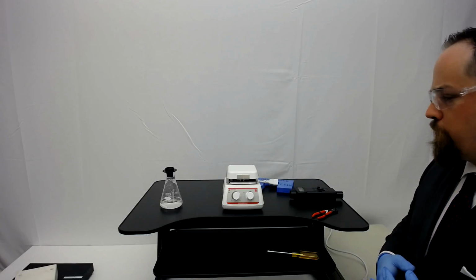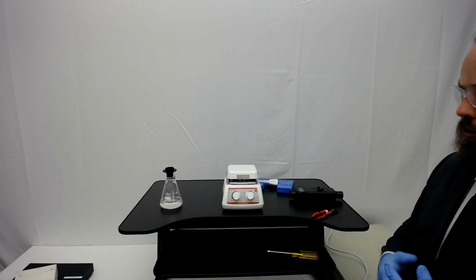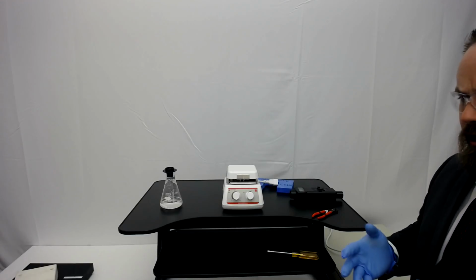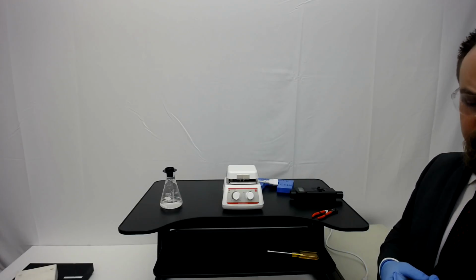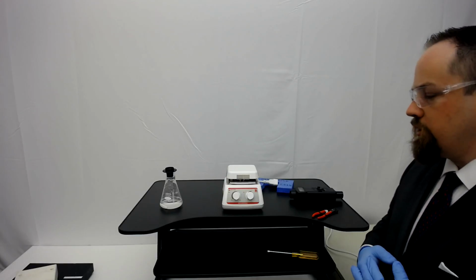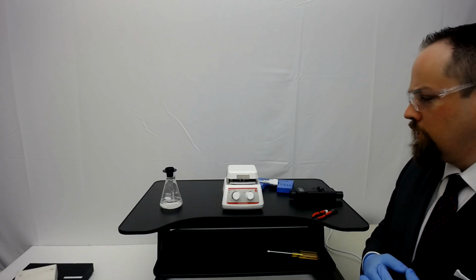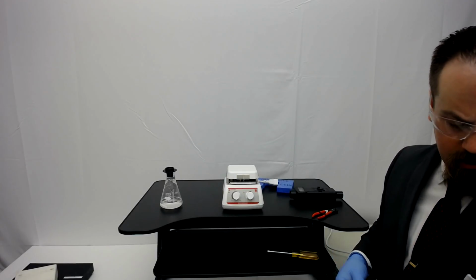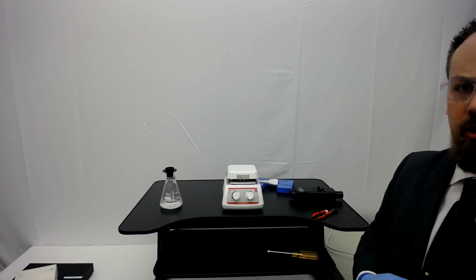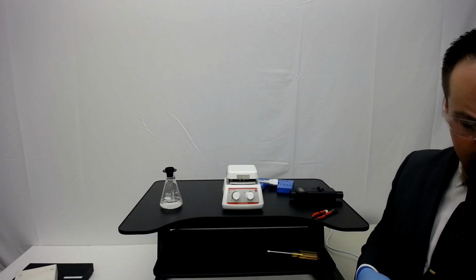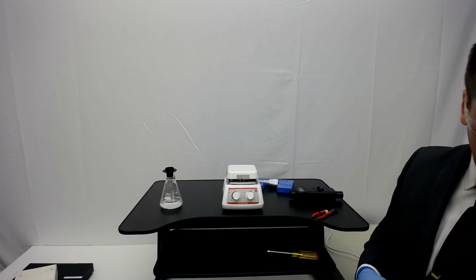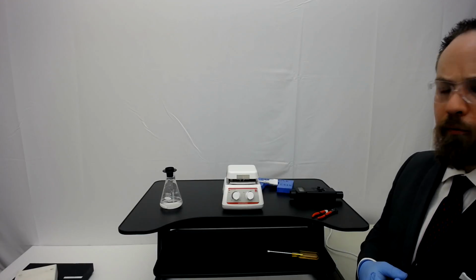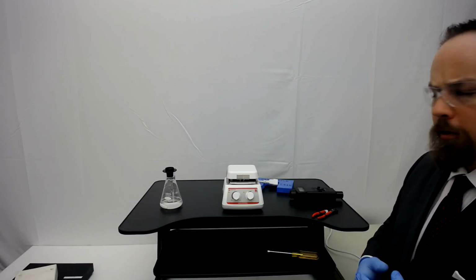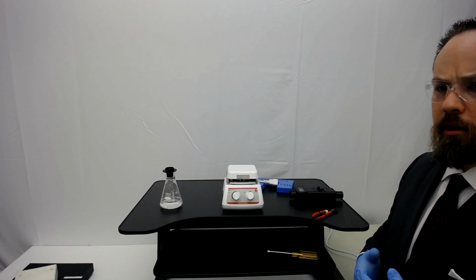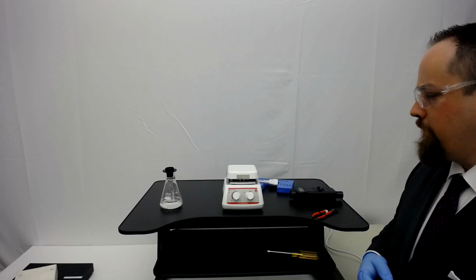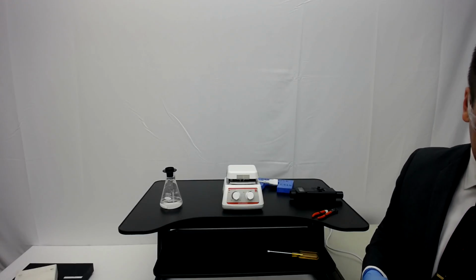There are tests for the hot plate function as well that we're not going through today. See your service manual for those. See your service manual also for the final testing and packing. All the units that we're going to be talking about today are going to need high pot testing before packing. Anytime you open or close one of these units, we're making sure that a high pot test is run on the unit.